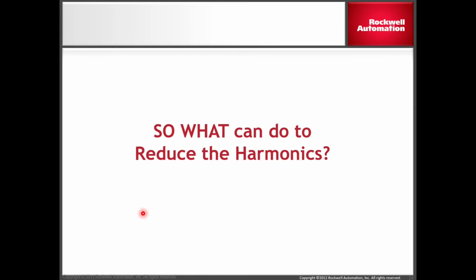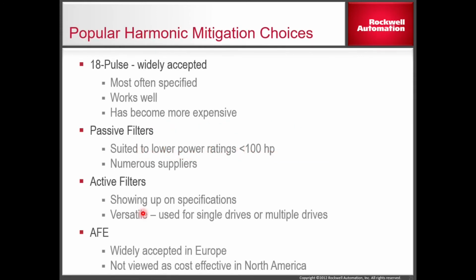So what can I do to reduce the harmonics? Well, there are several popular mitigation choices. We can put 18-pulse drives in, which, as a rule of thumb, usually you see that at 100 horsepower and up applications. We have passive filters, which are tuned to the 5th and 7th harmonic typically, because those are your biggest contributors to your overall total harmonics. We have active filters that act like noise-canceling headphones that attack all the harmonics being generated. And then you have active front ends, which is typically an active filter built right into the drive.